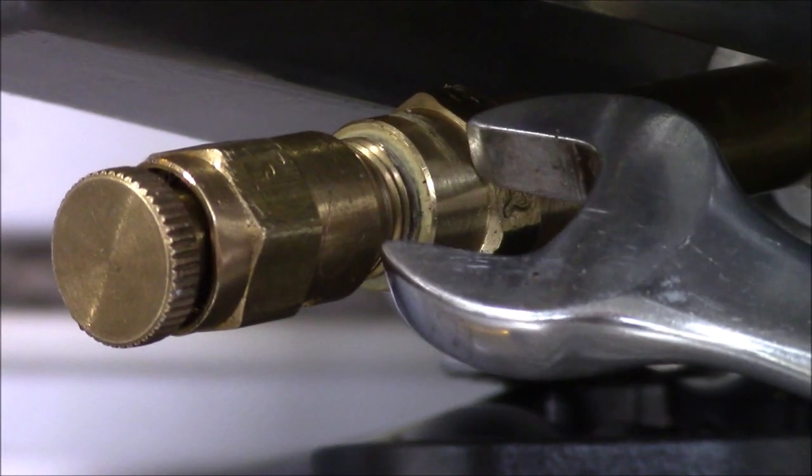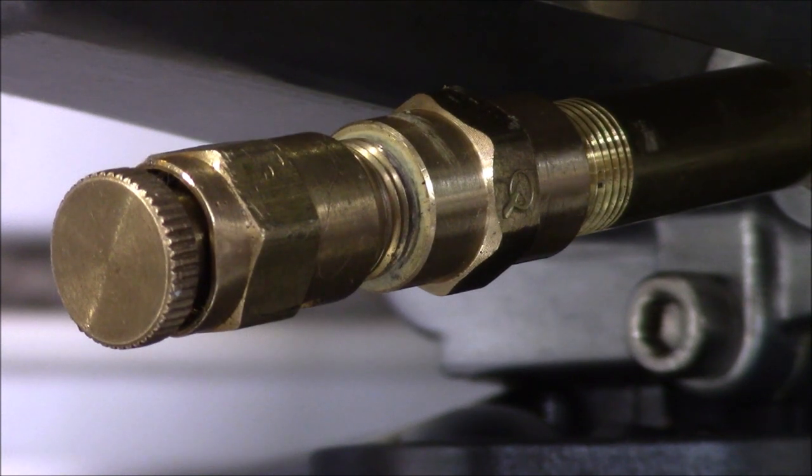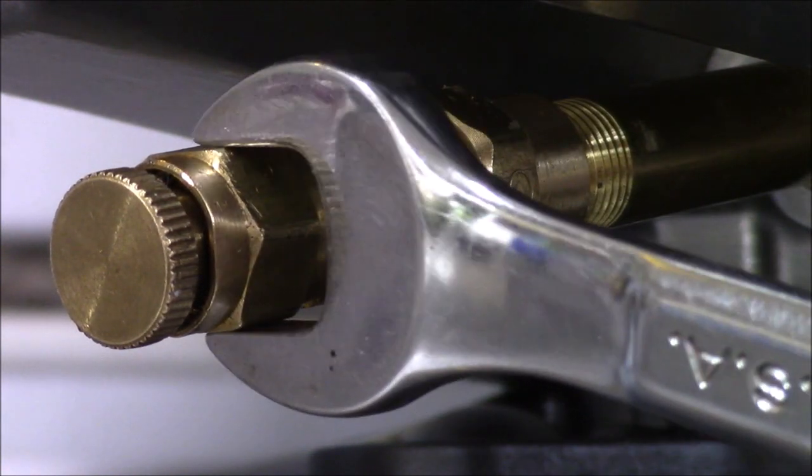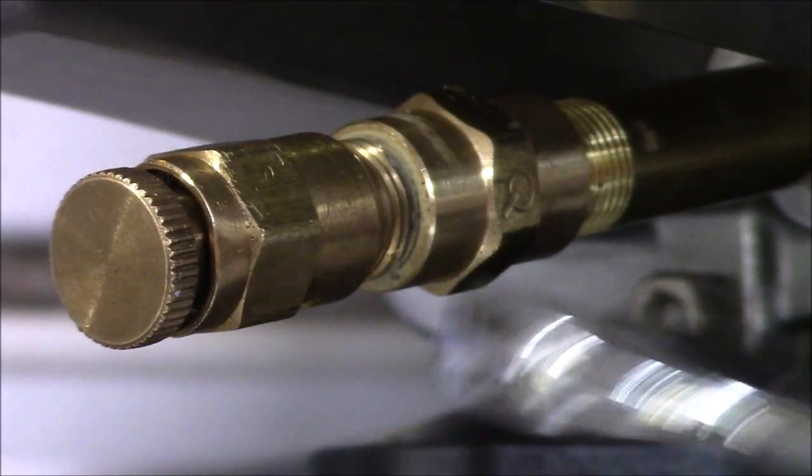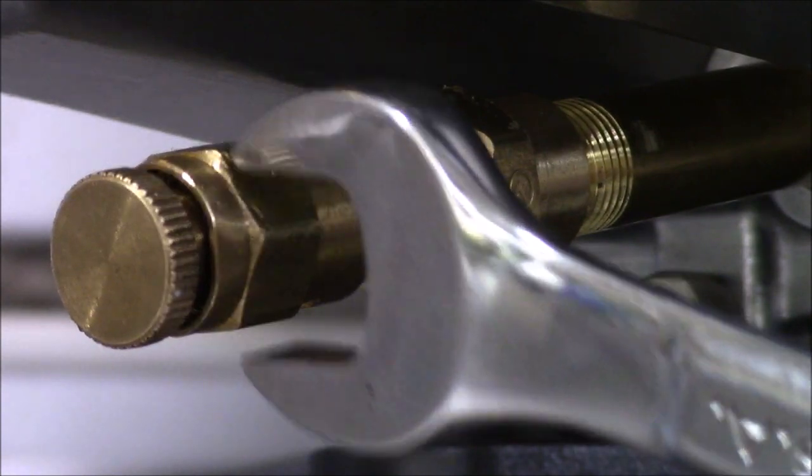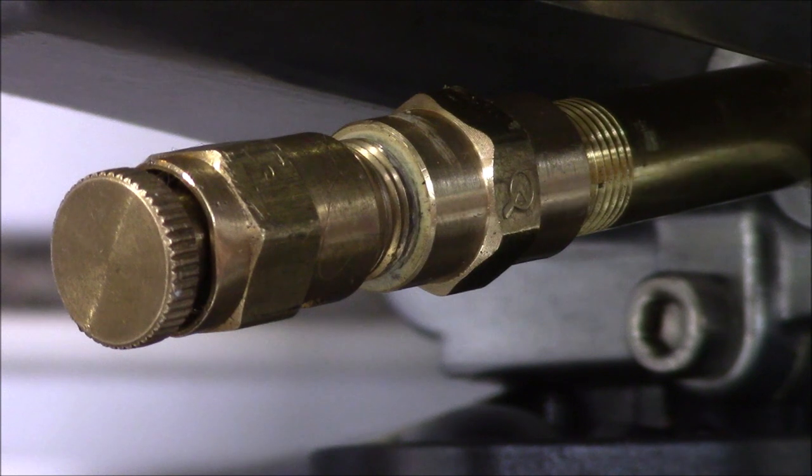You can see this is the coupling right here. That's the nipple right there, that's the coupling, and this is the actual drain valve itself. And you just look and get it good and snug, and turn this one right here, because when you turn this one, it'll actually tighten this up into here, and then tighten this up into there, and tighten it up into the unit itself.